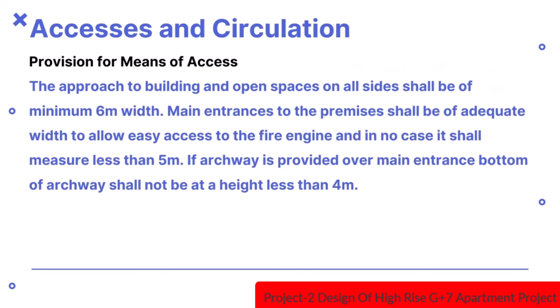Regarding accesses and circulation: the layout and design of spaces for horizontal and vertical movement may be planned suitably by adopting the following guidelines. The approach to building and open spaces on all sides shall be of minimum 6m width. The said open space shall be kept free from obstructions and shall be motorable. Main entrances to the premises shall be of adequate width to allow easy access to the fire engine and in no case shall be less than 5m.